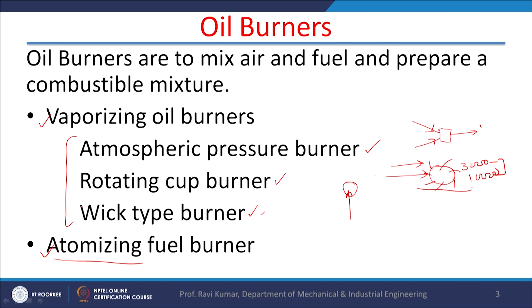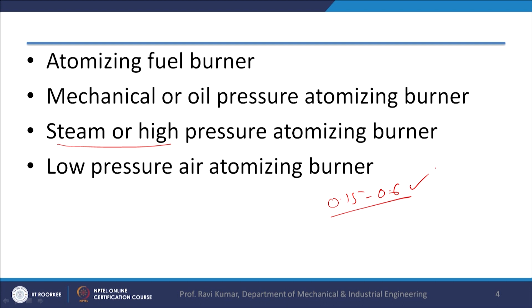Now, there are atomizing fuel burners also. In mechanical or oil pressure atomizing burners, the fuel is injected into a pool of air at very high pressure. So, atomization of fuel takes place, and this mixture is sent for burning. In steam atomizing burners, high pressure steam is mixed with the fuel, and then the mixture is injected for burning. There are low pressure air atomizing burners also for special applications, with pressure around 0.15 to 0.6 bar.